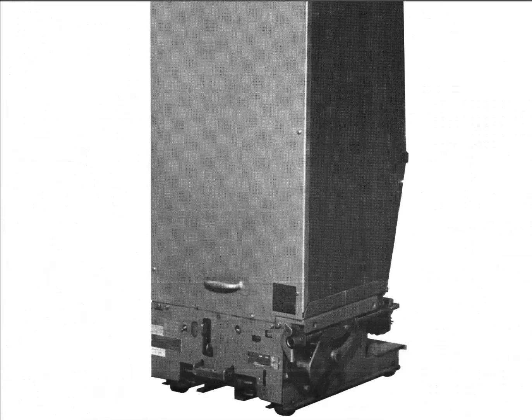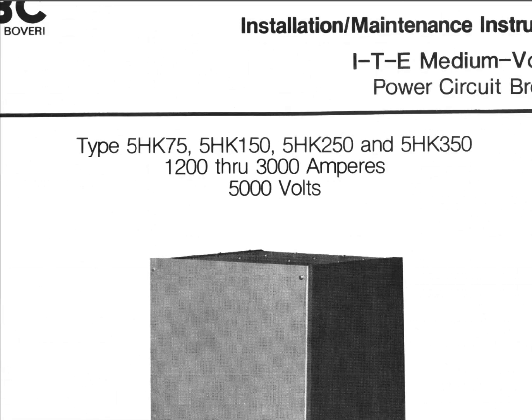Always confirm it matches your circuit breaker, or you're not doing your job. I'm sorry. You have to make sure that you have the right documentation. You can't just say, I've got a 5HK350. That's close enough. No, I mean, all your high pot numbers are wrong. Okay. If the second number over here, the 150, is a 250 instead of a 150, your millivolt drop checks are wrong. Okay. So you have to make sure that you have the right manual.